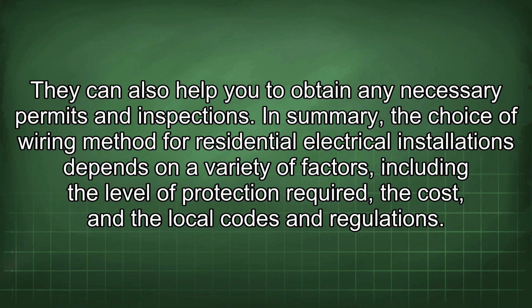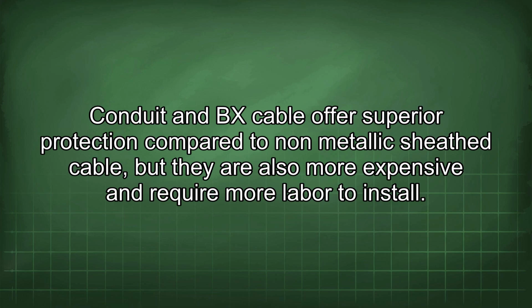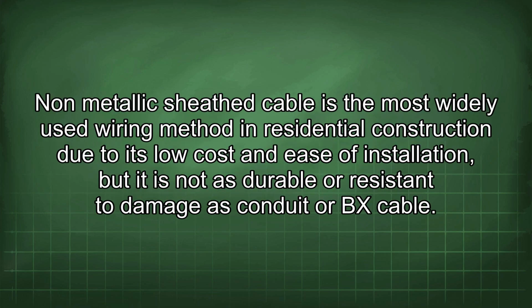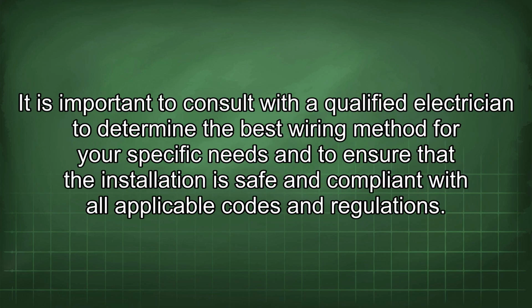In summary, the choice of wiring method for residential electrical installations depends on a variety of factors, including the level of protection required, the cost, and the local codes and regulations. Conduit and BX cable offer superior protection compared to non-metallic sheathed cable, but they are also more expensive and require more labor to install. Non-metallic sheathed cable is the most widely used wiring method in residential construction due to its low cost and ease of installation, but it is not as durable or resistant to damage as conduit or BX cable. It is important to consult with a qualified electrician to determine the best wiring method for your specific needs and to ensure that the installation is safe and compliant with all applicable codes and regulations.